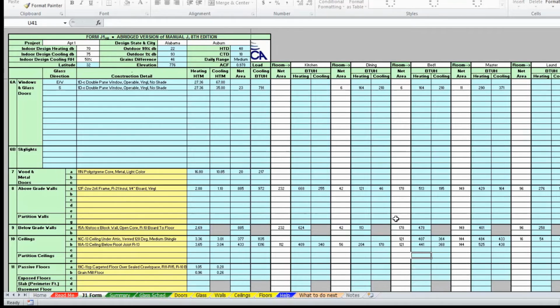Take a note to bedroom 1 and the master. I had accidentally put the area of the ceilings under the wrong category. Let's look at the master bedroom here, where we're working on the ceilings. I've got one ceiling under an attic, and another ceiling that's that roof sandwich. I had accidentally put the 144 square feet under the roof sandwich, giving us a heating load of 525 BTU per hour, when in reality it's only 484 BTU per hour, because I had put it in the wrong category.